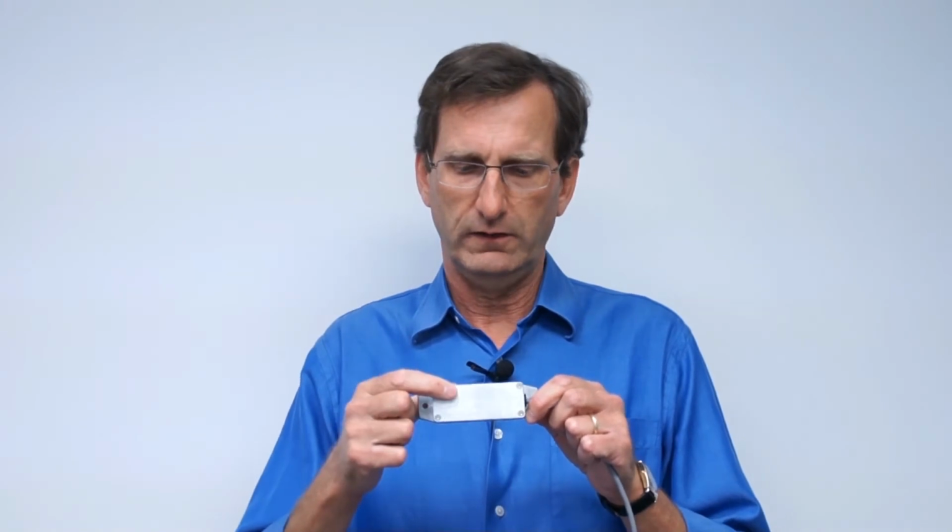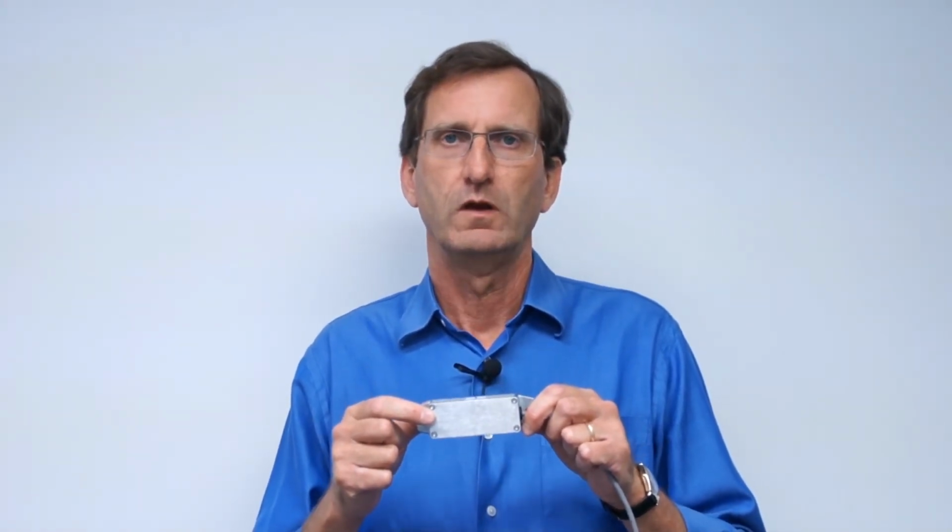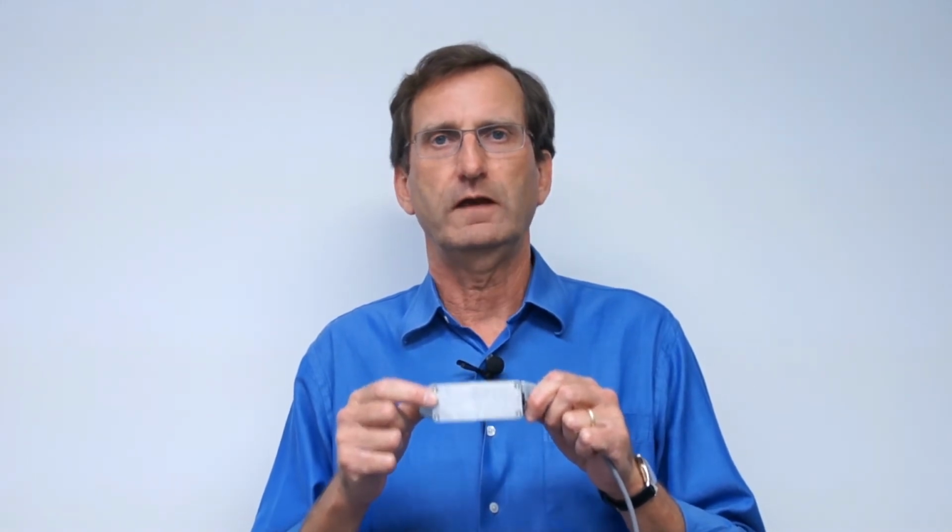For example, our vibration motor monitoring sensor. Inside of here is a 3-axis accelerometer and a microprocessor. This microprocessor samples G-force, or the vibration or the movement of this sensor, at 5 kilohertz. And it does that for 3 seconds. And it does it on 3 axes. That's generating a lot of data. 5,000 times 3 times 3 data points.